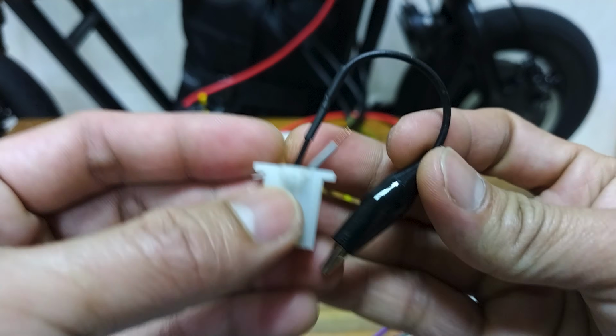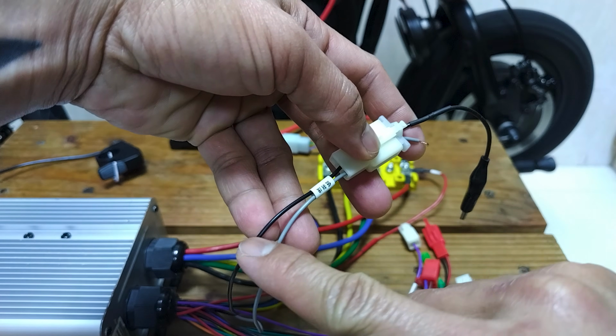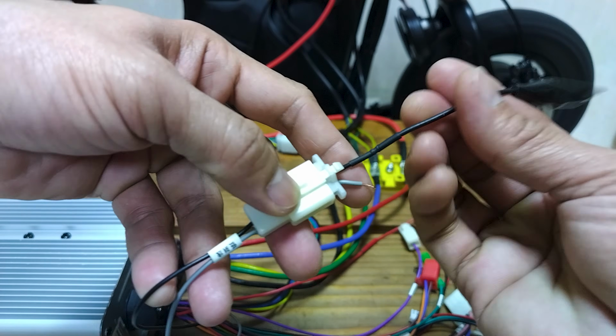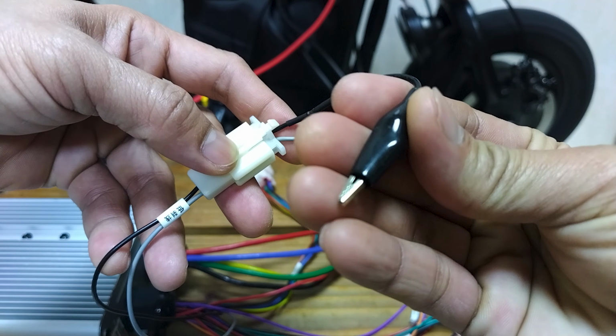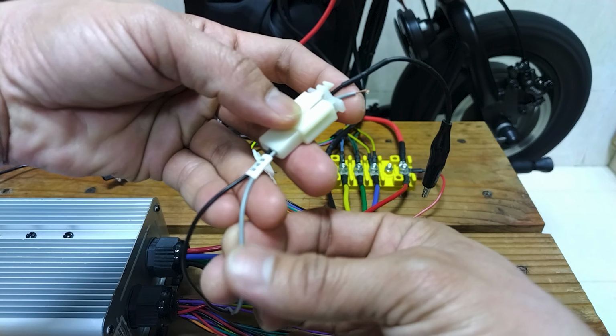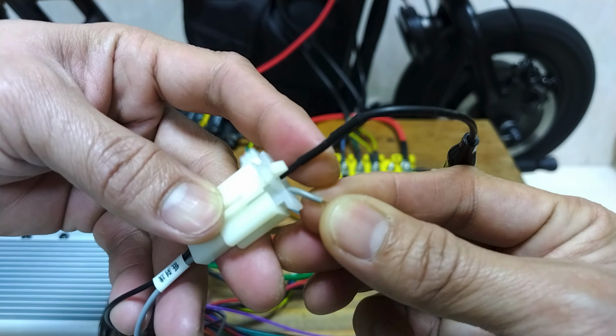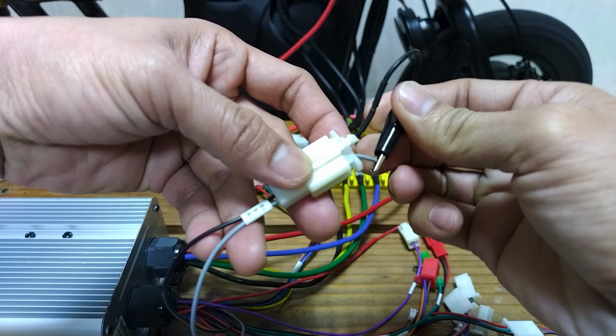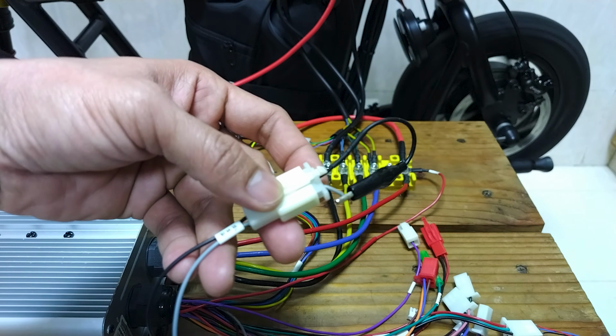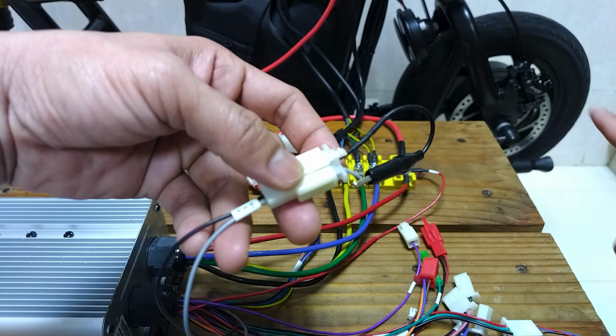I prepared this connector for easy example. As you can see, the black wire or ground wire is linked to the black wire that has an alligator clip, and the gray wire or signal wire is linked to the other wire. To activate the low brake signal, simply connect the ground black wire to the signal gray wire. The motor will then stop spinning.